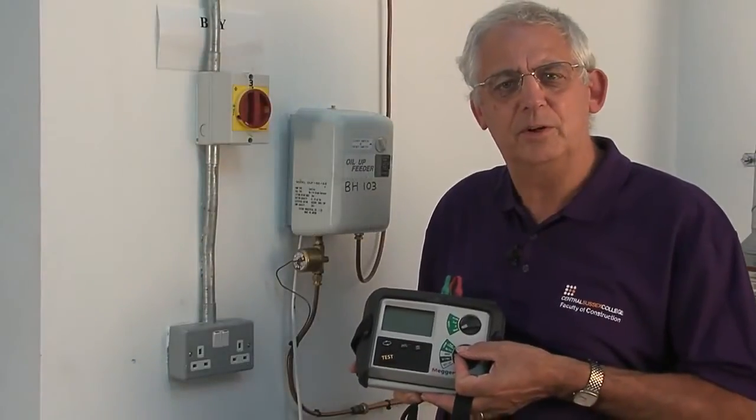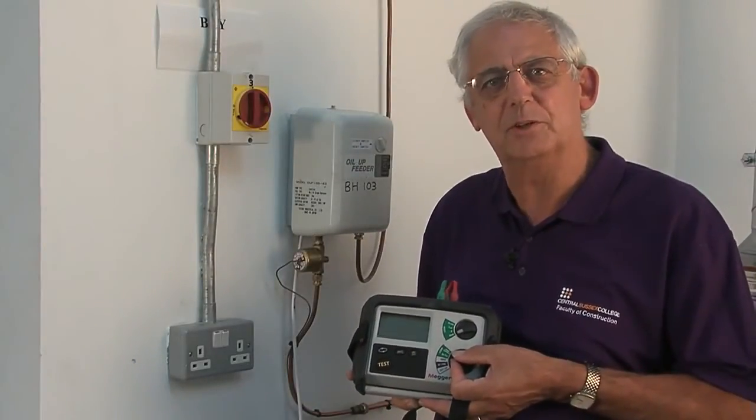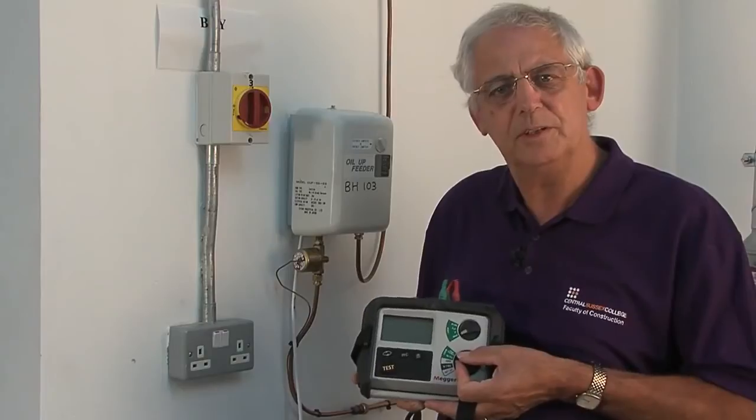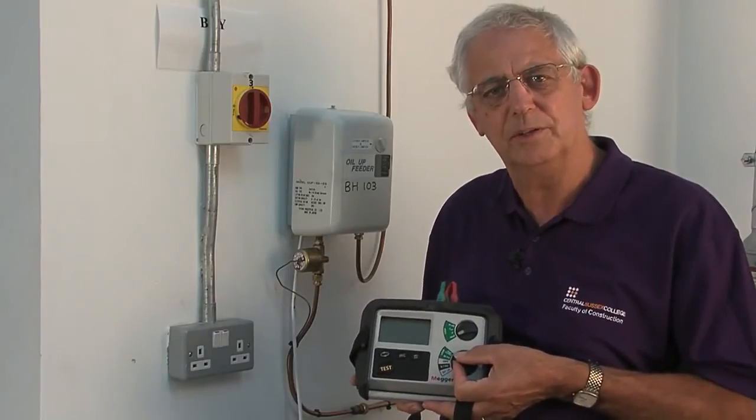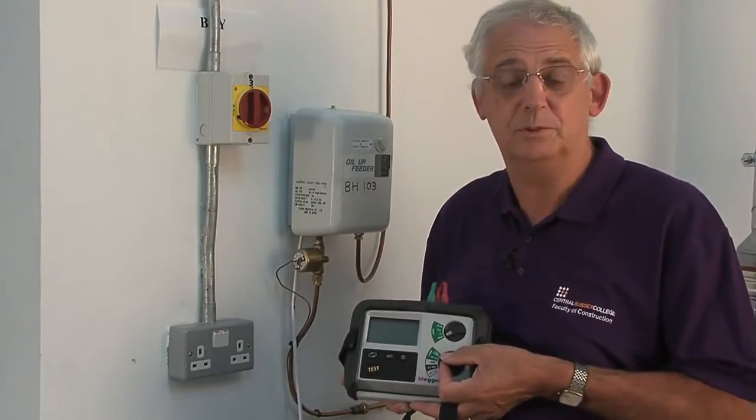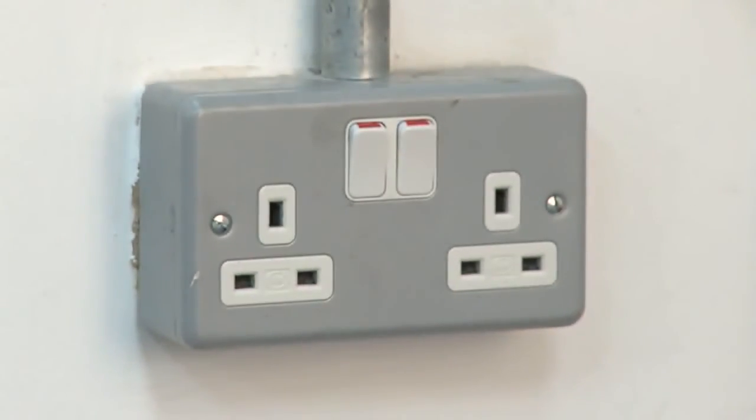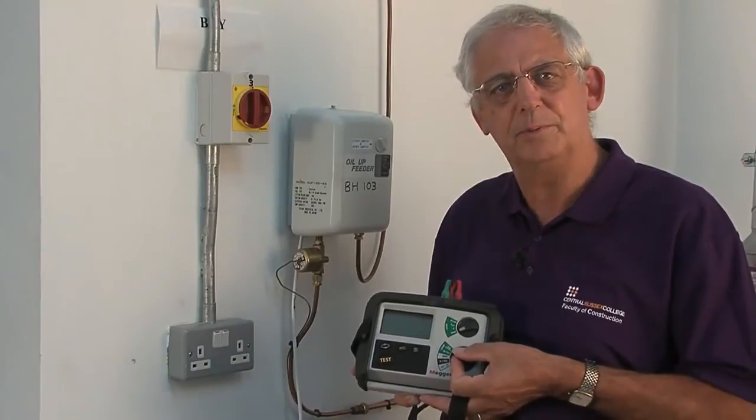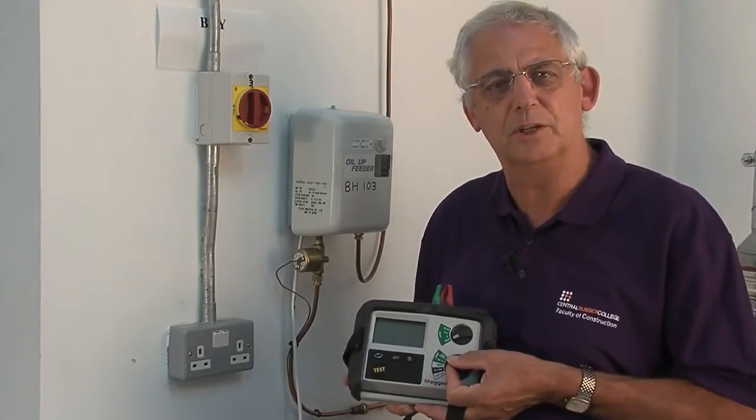We're going to carry out an earth fault loop impedance test on this socket outlet. The reason for the test is to ensure that the earth fault loop impedance, which we call ZS, is low enough to ensure that enough current can flow through the circuit to operate the protective device in the required time.